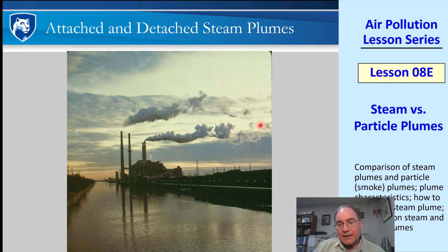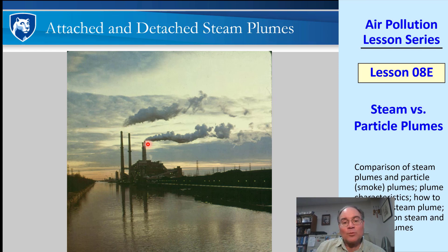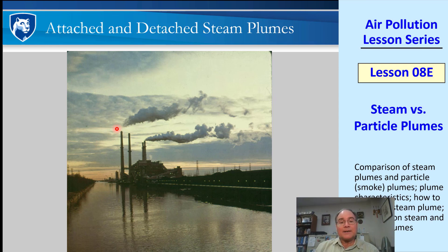This one is an attached steam plume and this one is detached. When a plume is buoyant, it comes out of the stack and levels off at some higher elevation; when there's no buoyancy, it goes straight across. The cooler plume has water condensing right at the stack exit — that's an attached steam plume. The warm plume takes some time to cool down enough to start condensing — once it condenses you start to see it, which is a detached steam plume.